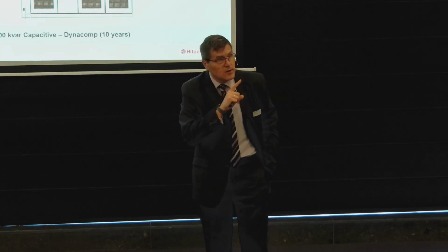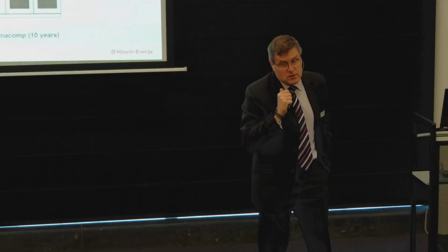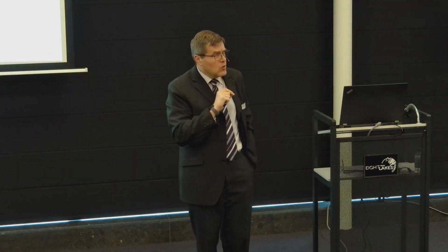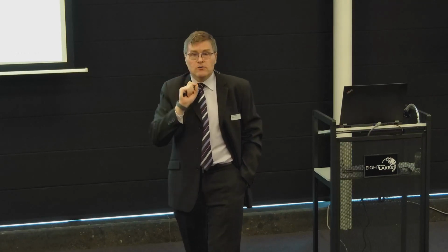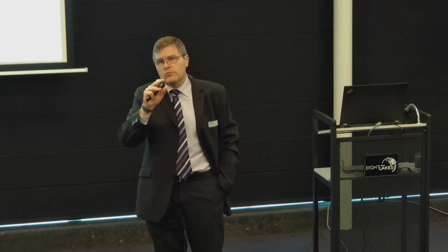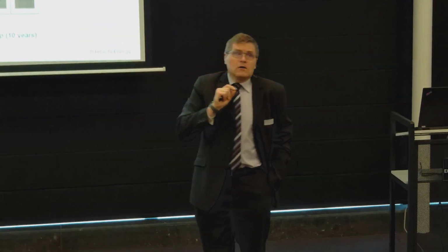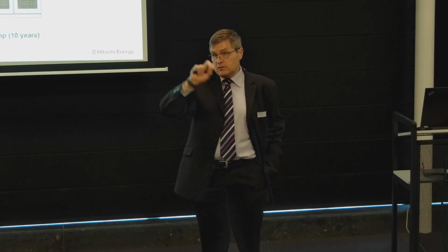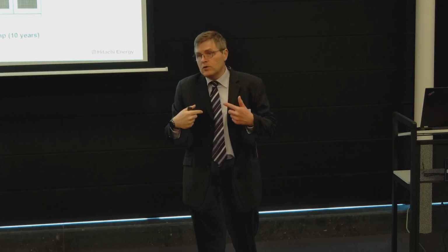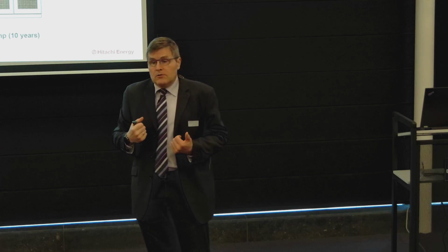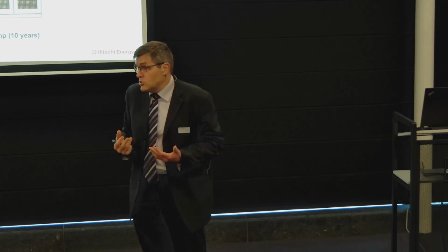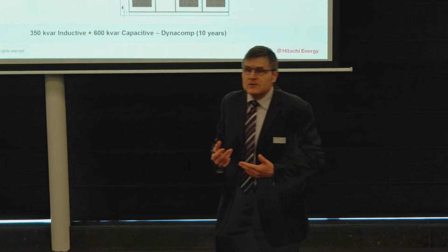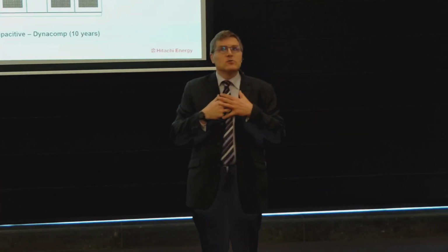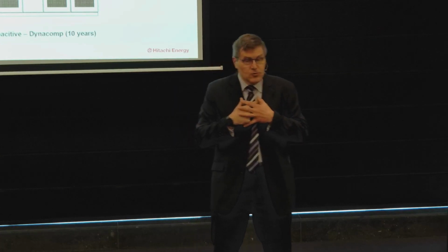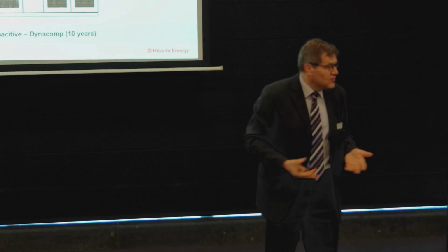Alors, here, with the grid connection, the solar plant owner got the authorization to connect to the Bulgarian grid only with a power factor nearly unity, 0.98 or 0.99. So, small comment, power factor is the target, and you have an energy meter, which counts the energy that you consume, active and reactive in industry. But you could have a cosinus phi 0, but if you have no energy consumption, you don't pay a penalty because your energy counter doesn't turn. So many customers come back to me, saying, oh, Olivier, I have a power factor 0.1, and I will die tomorrow. No, you will not die because you pay nothing. No current, no bill.